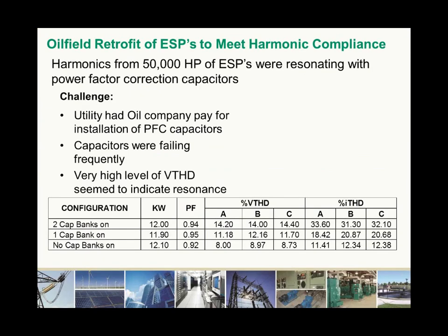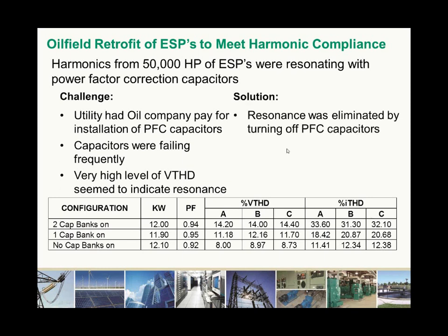Upon investigation, I found that the utility had previously installed power factor correction capacitors, unaware that the low power factor was due to the reactive power of the harmonic currents and not inductive loads. After significant effort, we eventually convinced the utility to switch off the PFC cap banks, and the results are shown in this table. When we have both cap banks on, voltage distortion was around 14%, and current distortion in the 30% range. We switched off one of the cap banks, the voltage distortion dropped a couple of percentage points, and the current distortion dropped significantly. When we turned off all the cap banks, voltage distortion was lowered to less than 9%, and current distortion was also lowered significantly. So we eliminated the resonance by turning off the power factor correction capacitors.